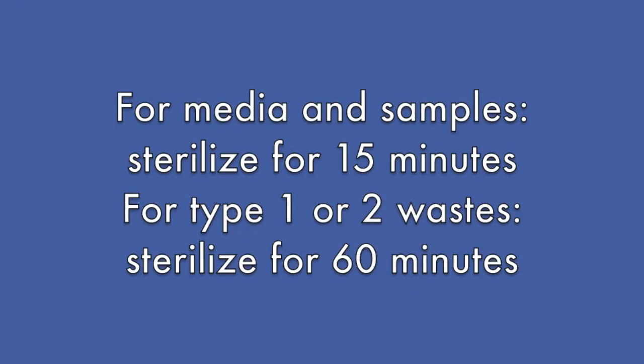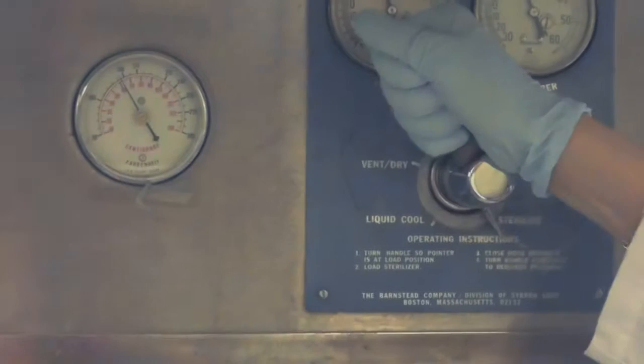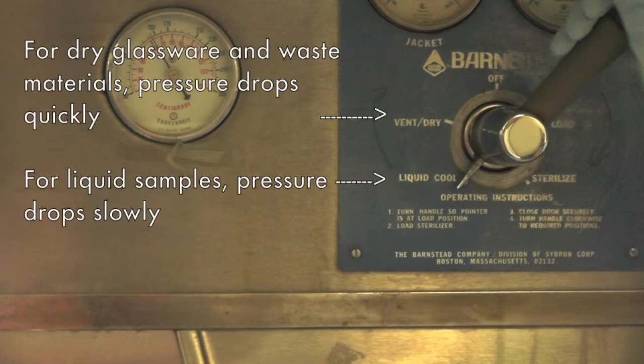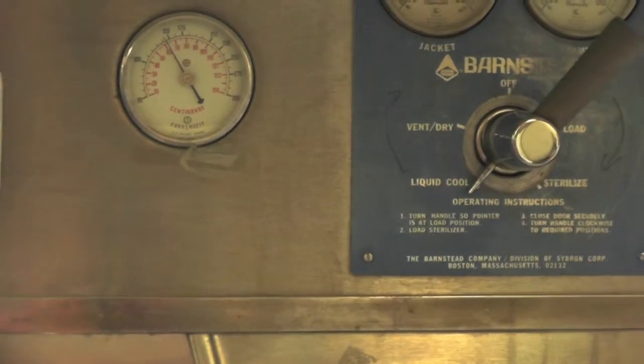Once the chamber gauge reaches 15 psi, manually time for 15 minutes if you are autoclaving agar and samples, or 60 minutes if you are autoclaving risk group 1 or 2 wastes. When time is up, turn the knob to liquid cool position for liquid samples, so the pressure of the chamber will be released slowly to 0 psi to avoid spillage caused by sudden pressure drop. Alternatively, if you are autoclaving dry glassware or waste materials, you can turn the knob to vent/dry position to quickly release the pressure to complete the cycle.